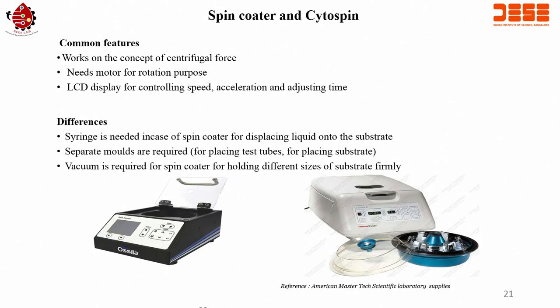So, what are the common features when I talk about spin coater and when I talk about cytospin? The common features are: both work on the concept of centrifugal force, both need a motor for rotation, and an LCD display for controlling speed, accelerating and adjusting time. Those are the common features. What are the differences?